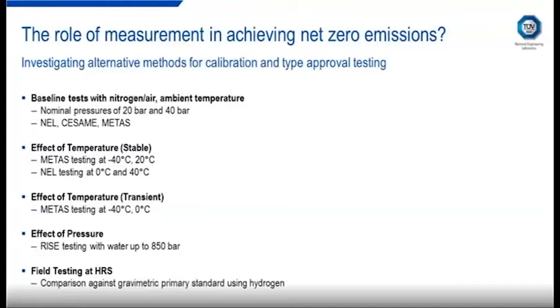The effect of pressure was also studied in isolation by the Swedish Metrology Institute RISE using water at up to 850 bar. And finally, a flow meter that had been tested using each of these test procedures was also installed at a hydrogen refueling station and tested under real conditions with hydrogen.